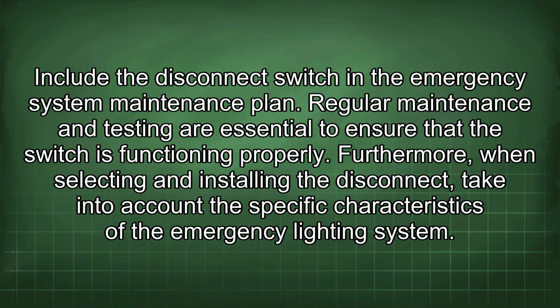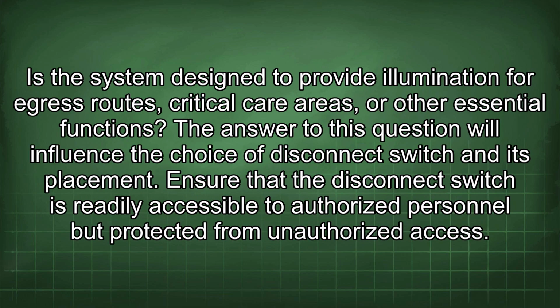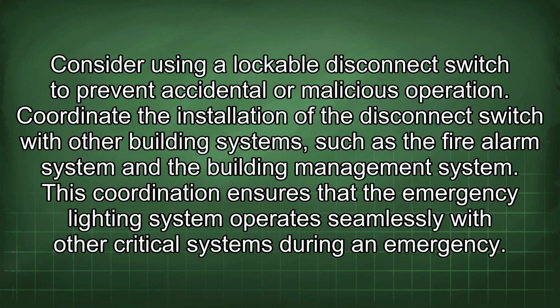Furthermore, when selecting and installing the disconnect, take into account the specific characteristics of the emergency lighting system. Is the system designed to provide illumination for egress routes, critical care areas, or other essential functions? The answer to this question will influence the choice of disconnect switch and its placement. Ensure that the disconnect switch is readily accessible to authorized personnel but protected from unauthorized access. Consider using a lockable disconnect switch to prevent accidental or malicious operation. Coordinate the installation of the disconnect switch with other building systems, such as the fire alarm system and the building management system. This coordination ensures that the emergency lighting system operates seamlessly with other critical systems during an emergency.